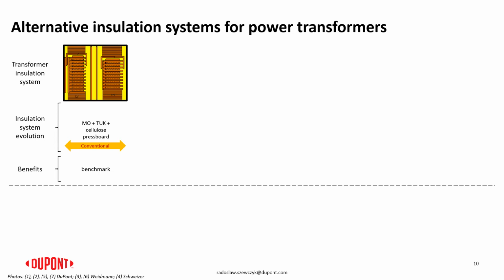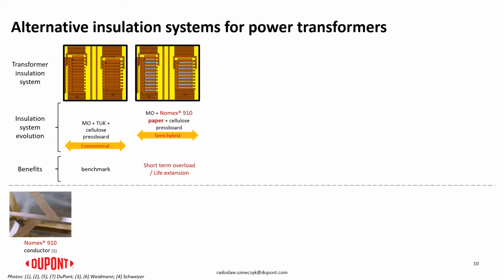And when looking at the broader overview of various insulation systems available, we could start from the conventional insulation system, and this is the sketch, or the charts are based on the typical disc winding power transformer, where the conductor is insulated with the cellulose paper, and the spacers and the end insulation system is based on the cellulose. If we go higher with the performance of the insulation system, we could talk about the new paper Nomex 910 used for the conductor insulation, which would provide some life extension and improved short time overload capability for the transformer.